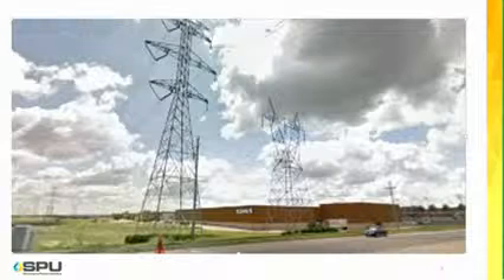At the nearer tower, the taller one with a more narrow profile, in the foreground, if you look close at the cross arms on the metal superstructure, on the left-hand side there are double insulators forming a V, holding up the wires on each of the three levels for each phase, and that's 345 kV. On the right side of that tower, you can see a single insulator on each of the three arms with a smaller string of insulators, indicative of a lower voltage.